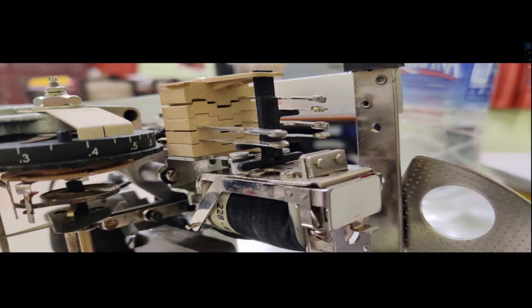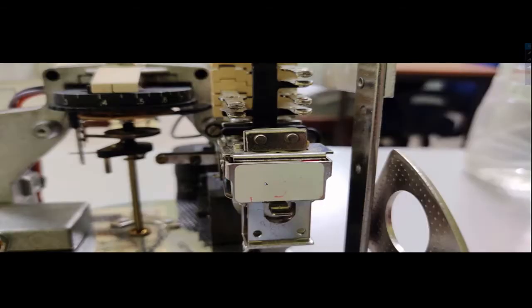So this will attract that plunger. One small plunger is there inside this one. Once the DC power is flowing through this one, this plunger is attracted towards it, and once it is attracted, this black portion goes up, and once the black portion goes up, the normally open switch becomes closed. You see this is a normally open switch, no connection is there, but when this one is energized, it will attract the plunger towards it, so this black portion goes up, and it will ultimately short circuit this particular portion, and the trip signal will be generated, which will activate the circuit breaker later on. And this is the plunger. This one is the plunger which will be attracted by the solenoid type tripping coil once this portion is closed by that particular arrangement.